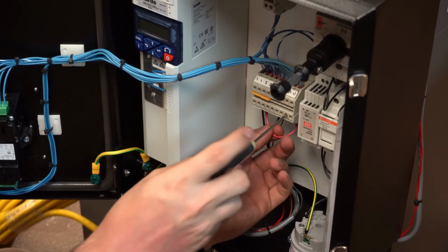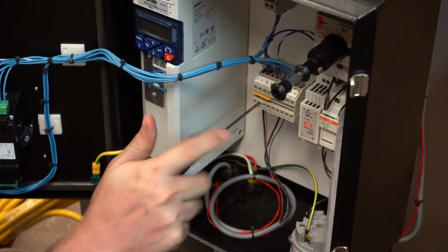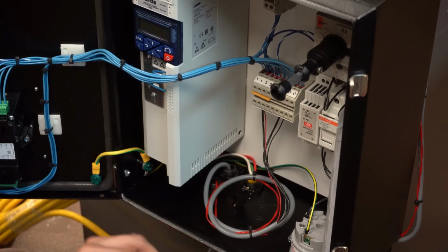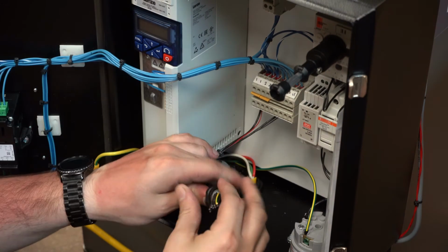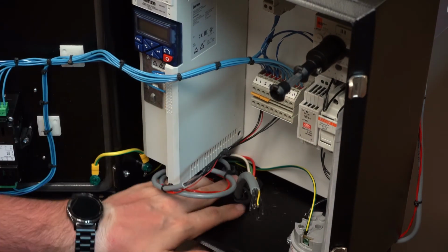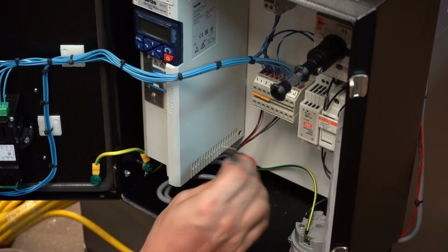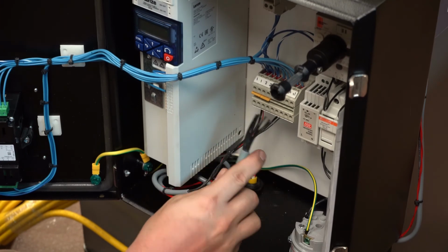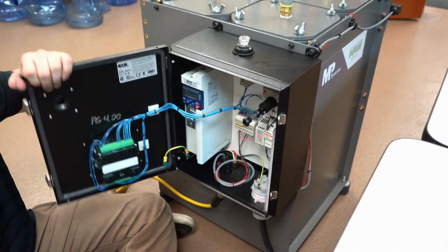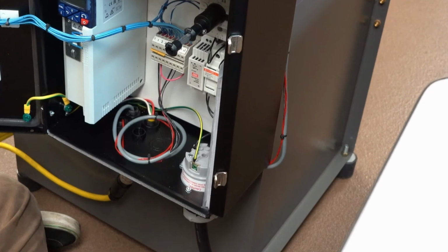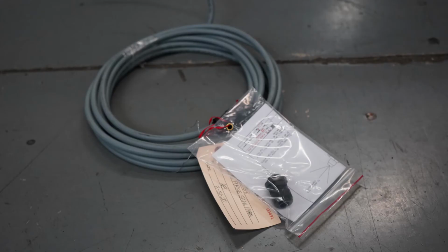Remove the pink jumper from pins 1 and 10. Run the interface cable into the bottom of the panel and tighten the cord grip. Then connect the wires into the respective pins on the terminal strip, 1 to 1, 2 to 2, and so on. Also found inside of the electrical cabinet are the schematics that the unit was built to that can be used as a reference when connecting the interface cable or troubleshooting the unit.